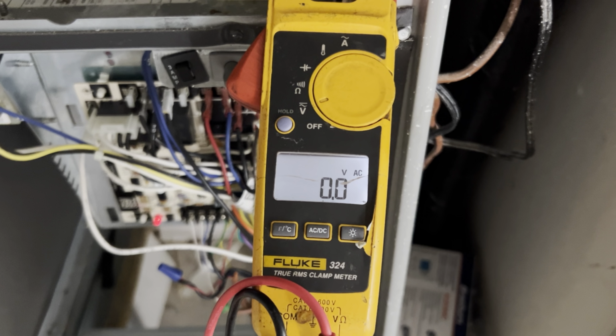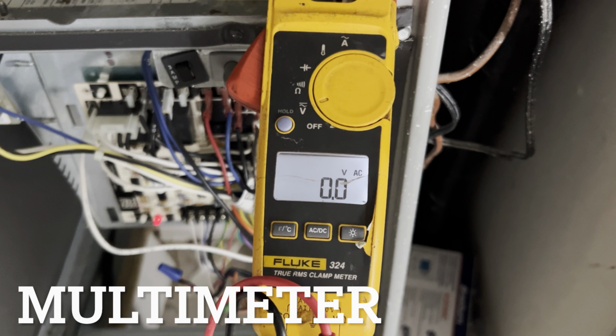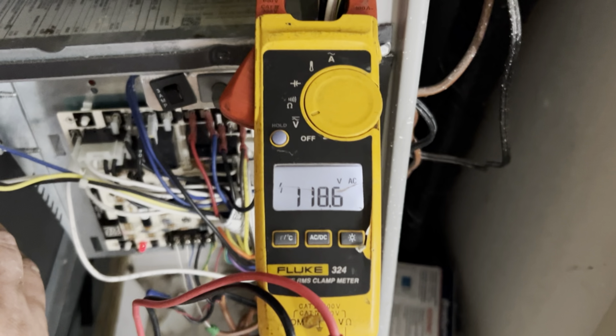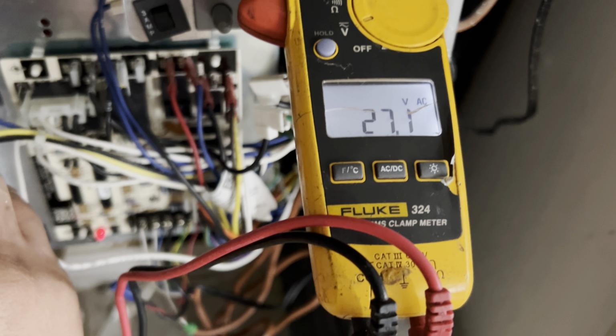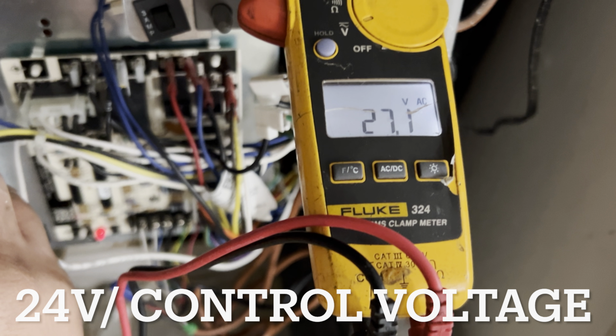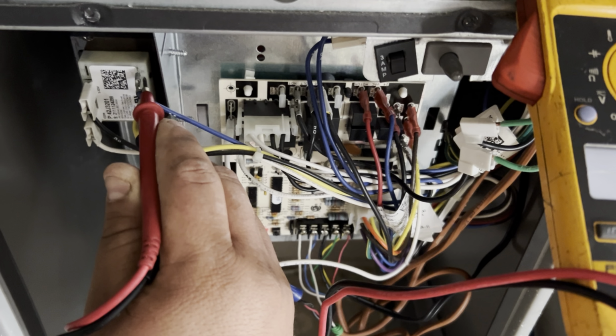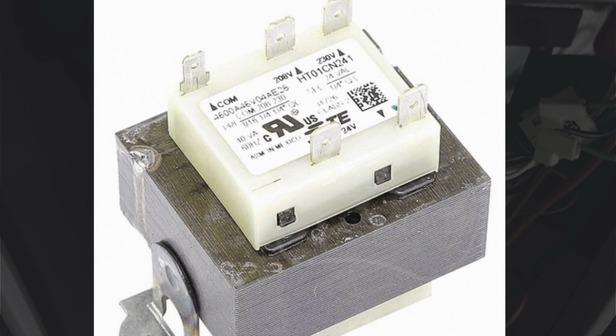Speaking of low voltage, the next part will require a multimeter in order to test the transformer. The transformer actually has 2 voltages. The primary voltage, or the high voltage, in this case 120 volts, goes into the transformer, and coming out will be low voltage or control voltage at 24 volts between the blue and yellow wire. If you have high voltage going in but no low voltage coming out, the transformer will need to be replaced.